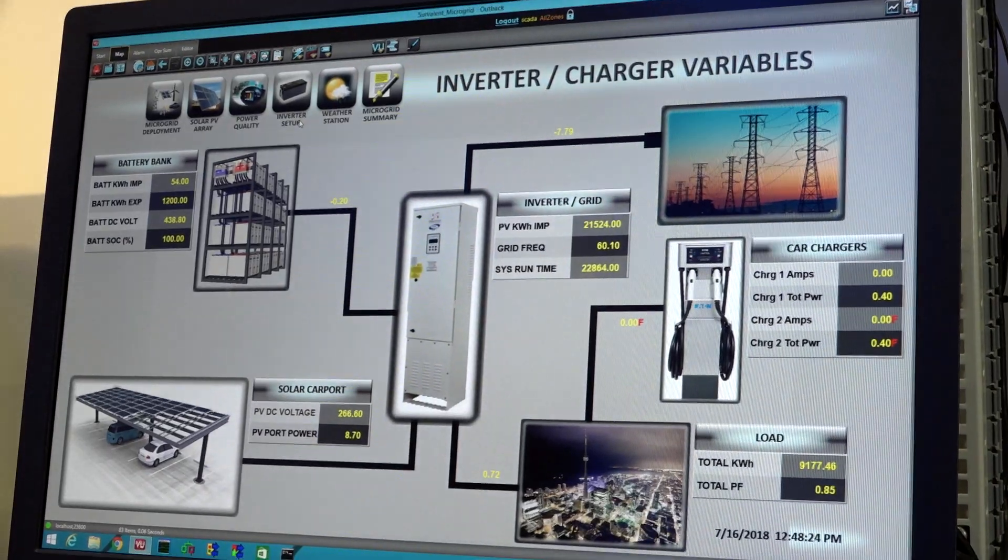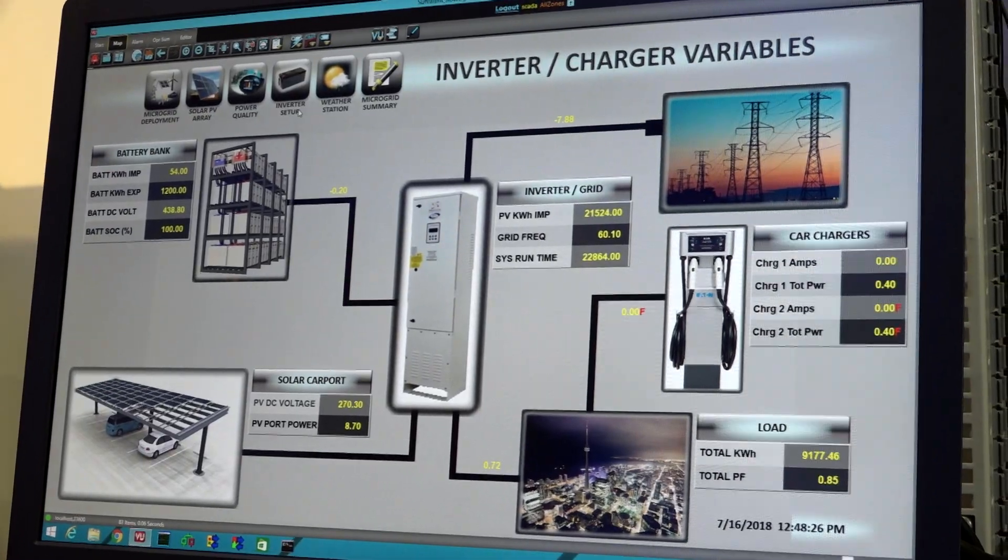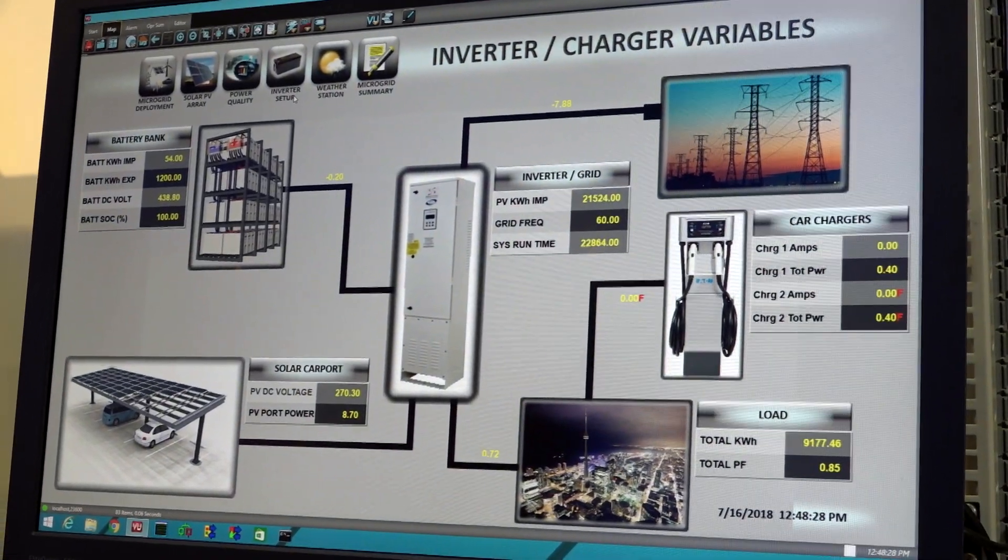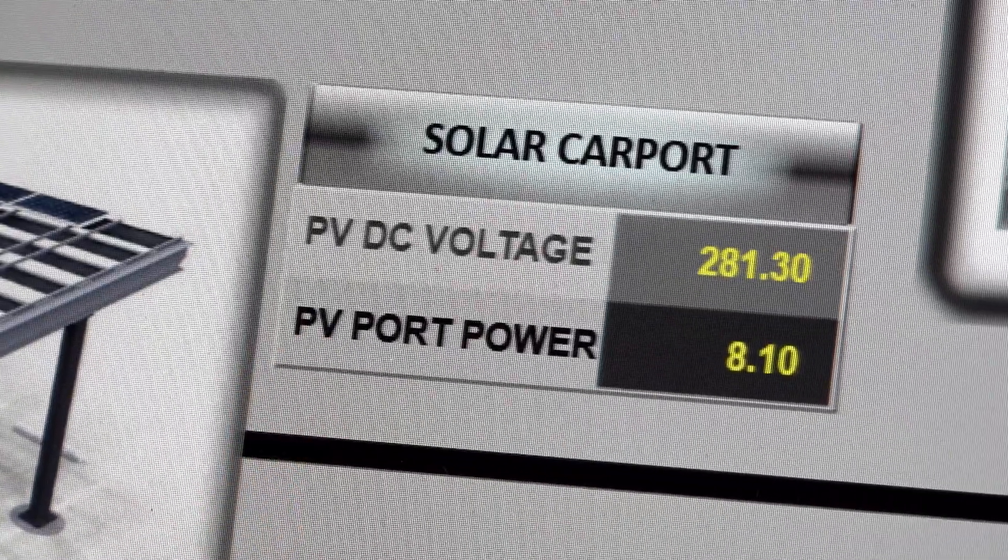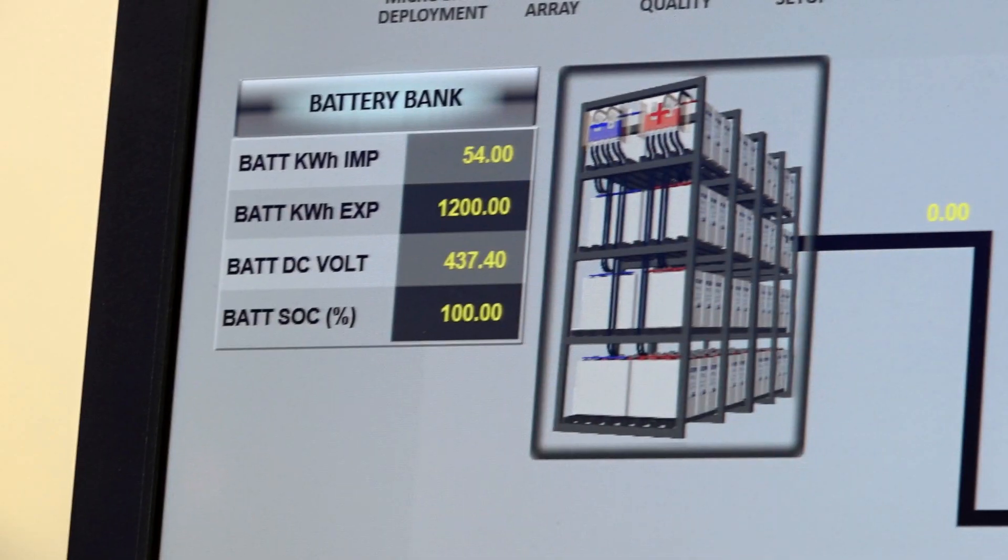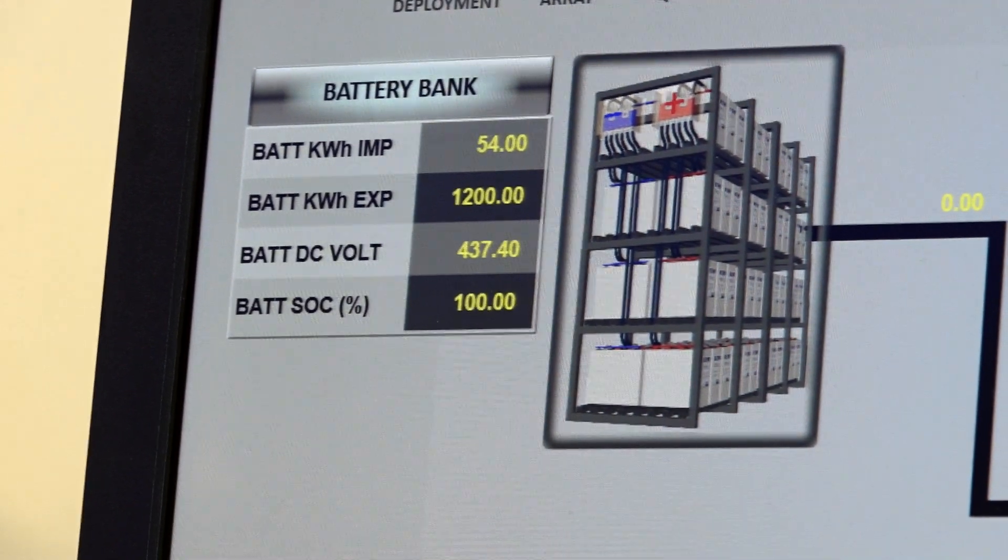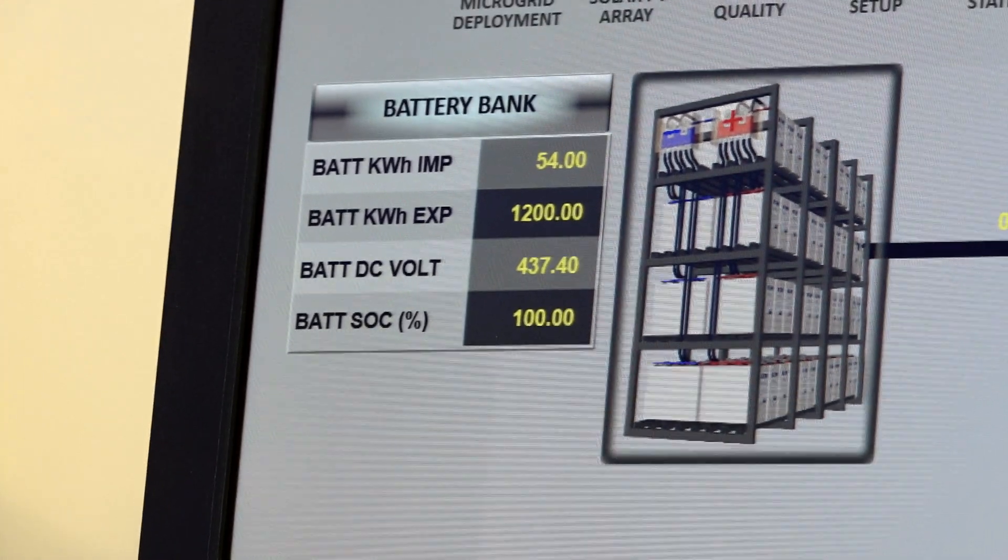All right, let's take a look and see where all that power is going. We are producing about eight kilowatts. And to put that in context, the building here, a day like today, is going to peak around 500 kilowatts. So on a good day, we only provide about 2% of what the building needs from the solar panels.